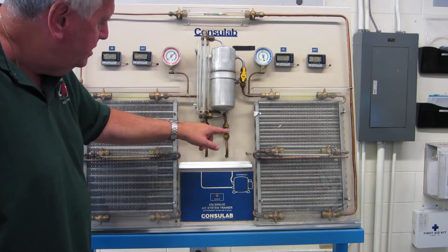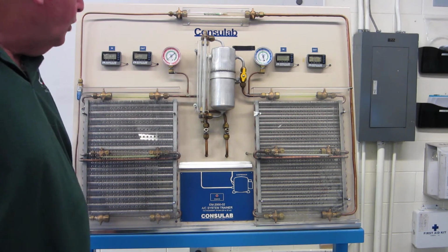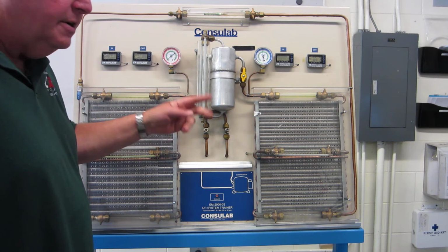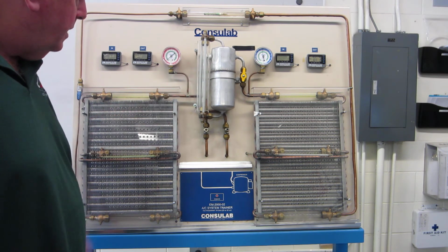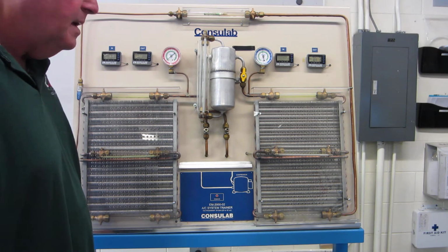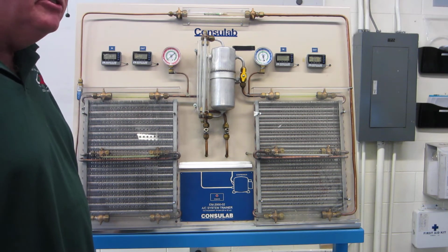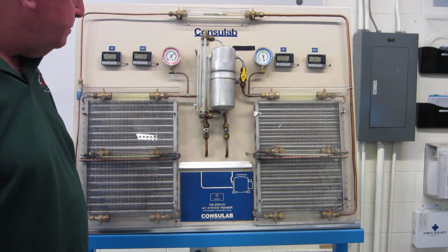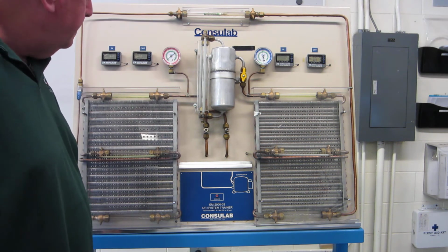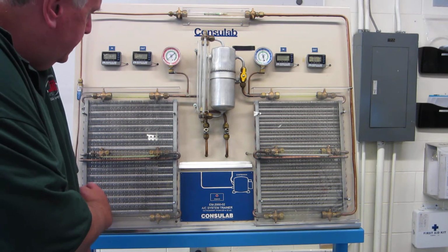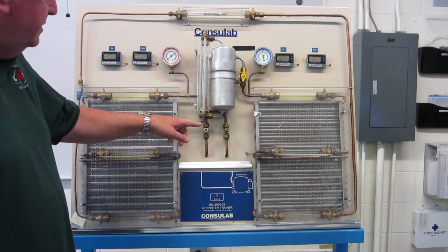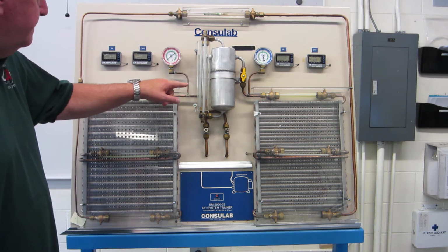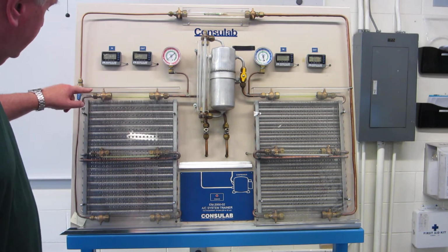So again, now going into the compressor, we have a low temperature, low pressure vapor. The compressor again does two things for me. One, it's going to pump the refrigerant through the system, but the biggest thing it does is actually raise the pressure. And by raising the pressure, we raise the temperature of the refrigerant. And now we're able to give up that heat energy quite easily to ambient air. So that means coming out of the compressor now, we'll have a high temperature, high pressure vapor. And it goes into the condenser.